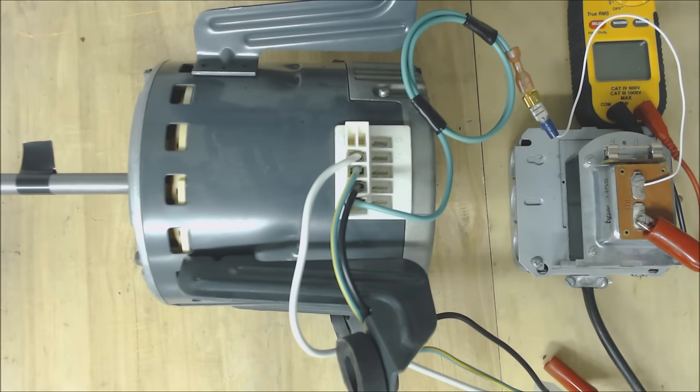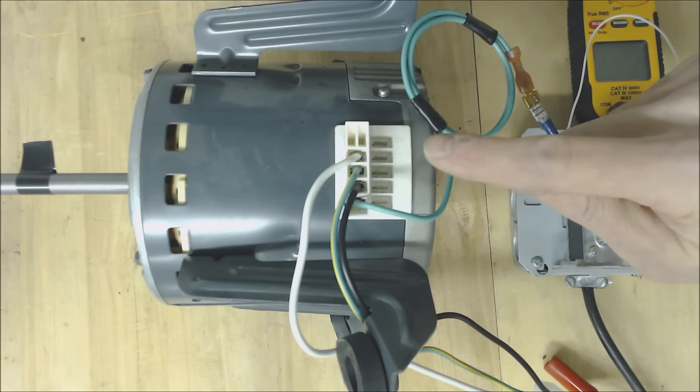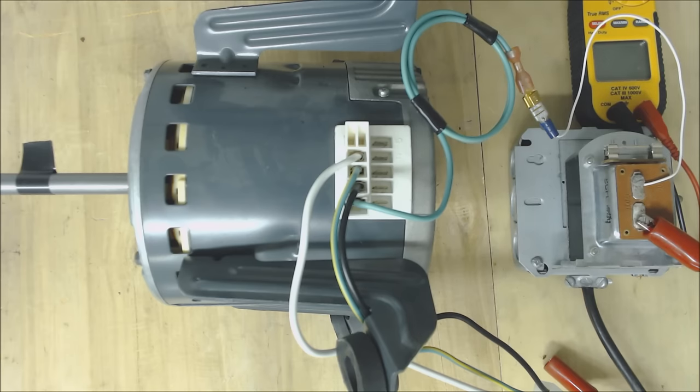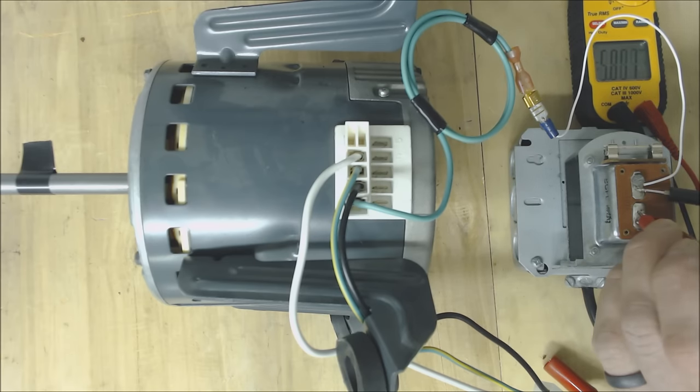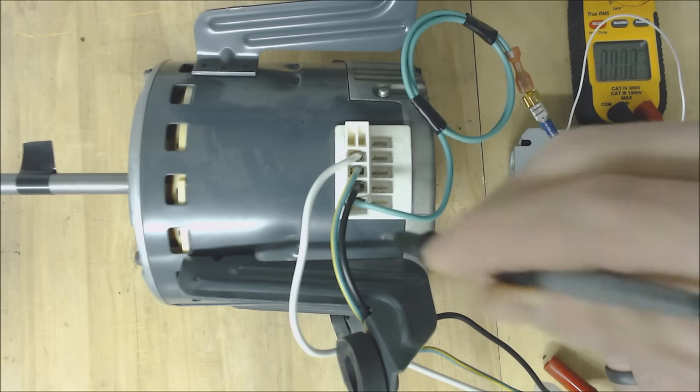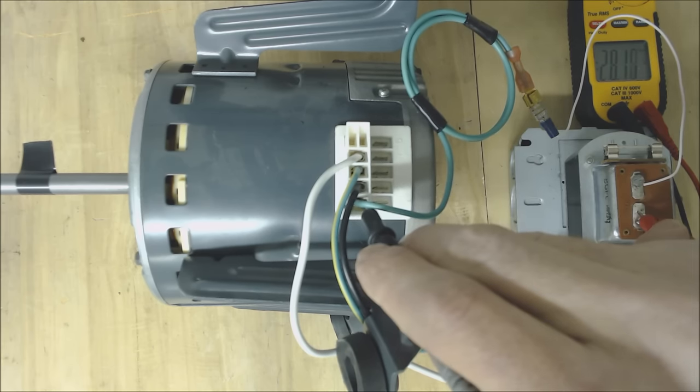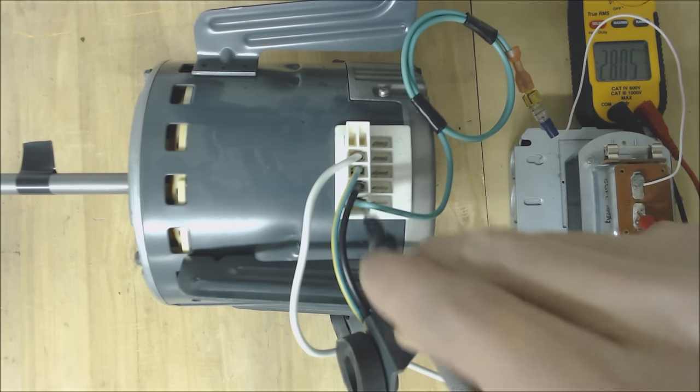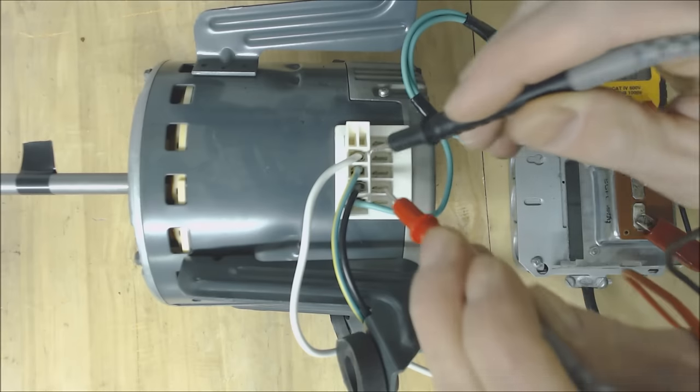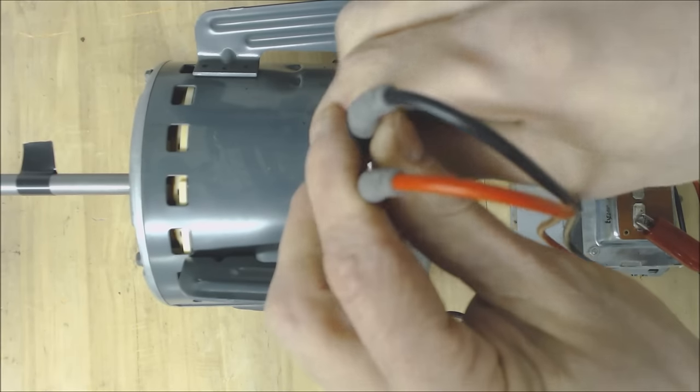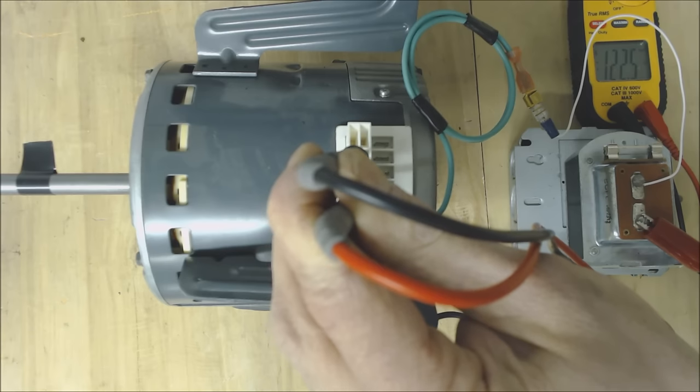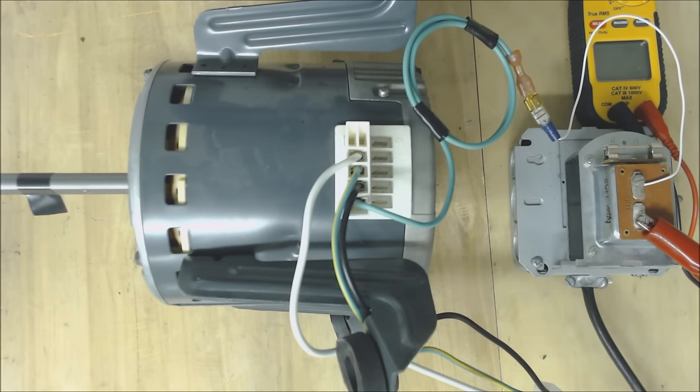Now we're plugged in so our transformer should have power and our 120 volt X13 blower motor should have power. We're going to read our voltages. 28 volts there, 28 volts there, and 122 volts which is correct.